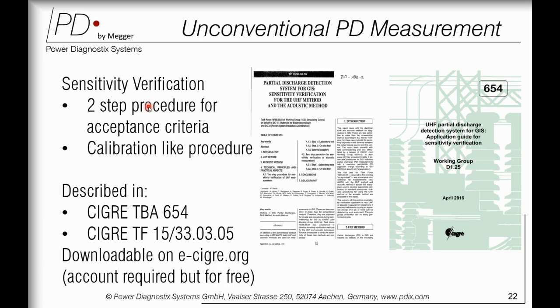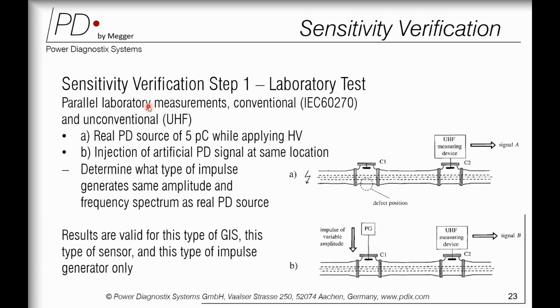So let's move on and discuss this CIGRE document. What they say is that in sensitivity verification there are two steps. Step one is done in the factory. First, they do a complete setup as per IEC 60270, and they put a known defect of 5 pC in the GIS and energize it.